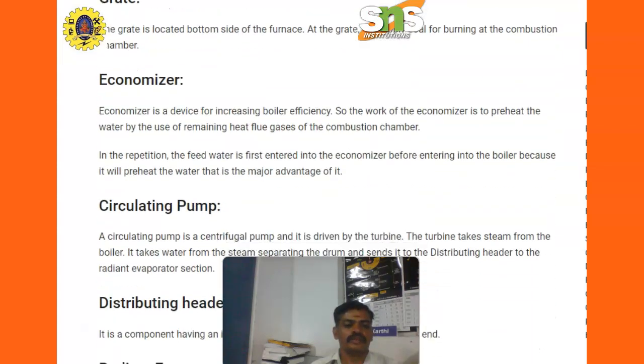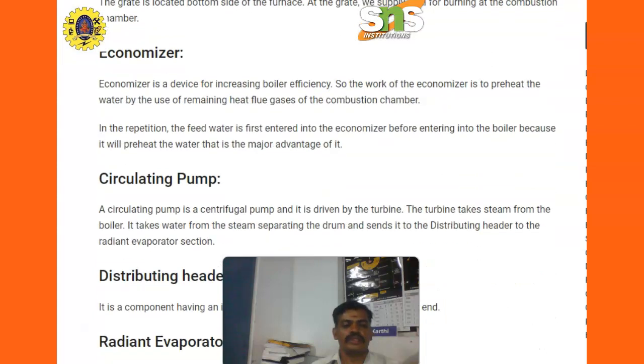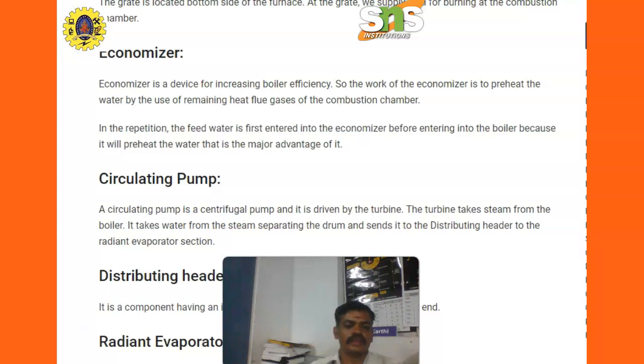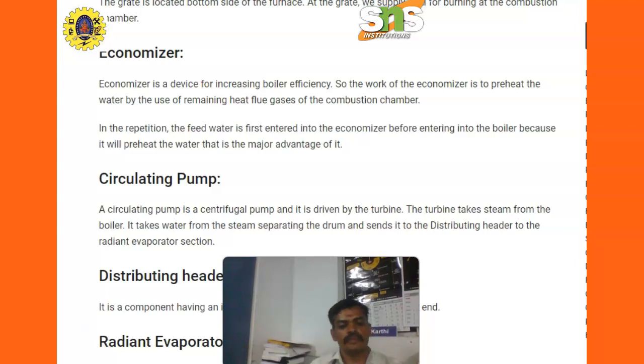Next is the economizer. The economizer is a device for increasing the boiler efficiency. The work of the economizer is to preheat the feed water by using the remaining heat from the gases of the combustion chamber. The feed water is first entered into the economizer before entering into the boiler, because it will preheat the water — that is the major advantage.